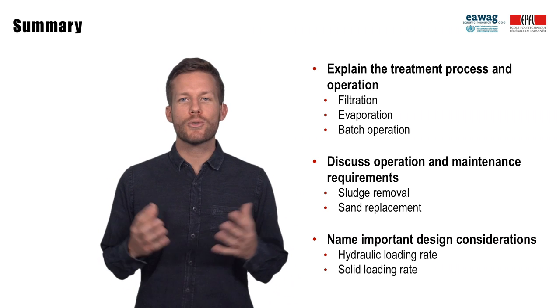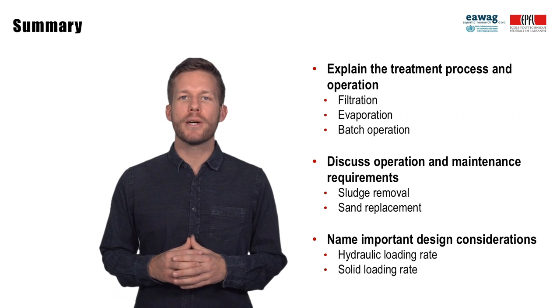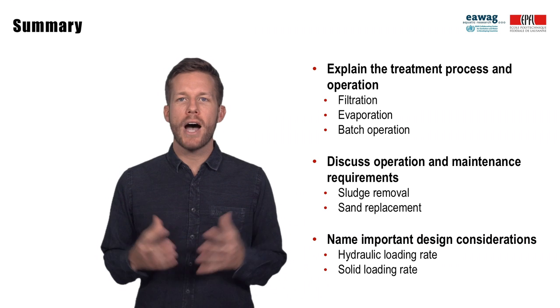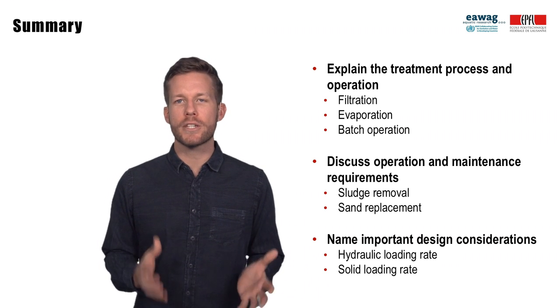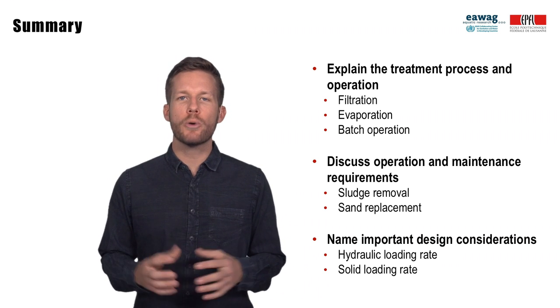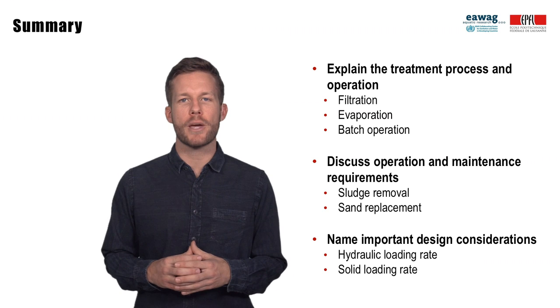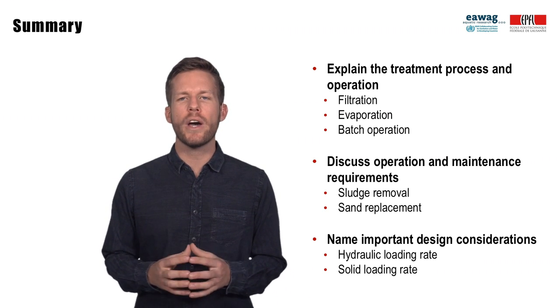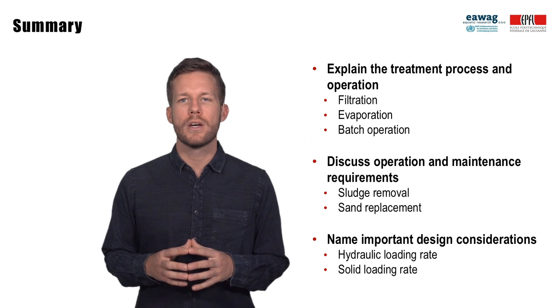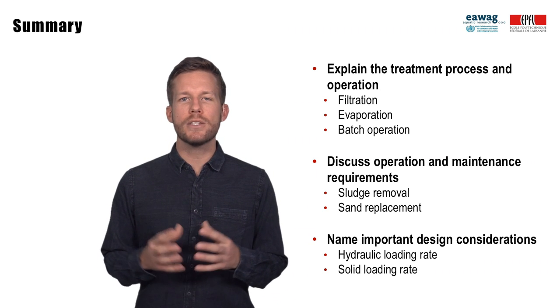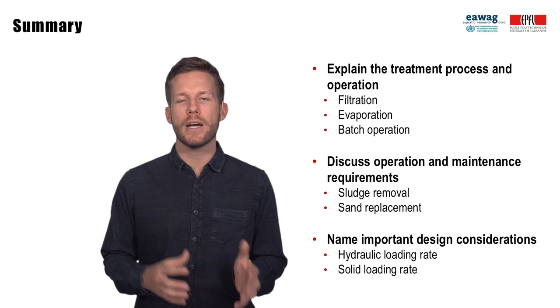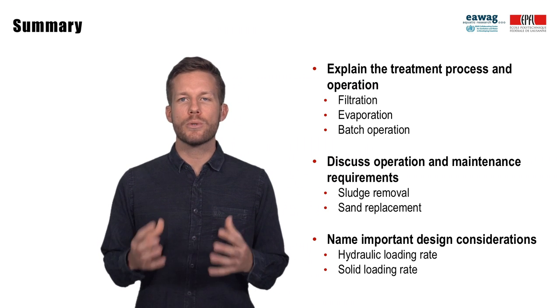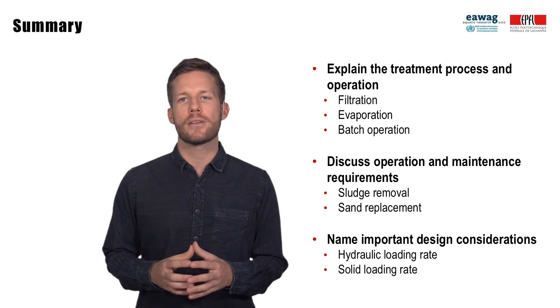In this module, we learned that the treatment process of unplanted drying beds is based on filtration and evaporation. Unplanted drying beds operate in batch mode and require removal of sludge from the surface of the drying beds. In addition, the replacement of the sand filter layer is required for reliable operation. Drying beds need to be designed based on the local climate and sludge characteristics. The most important design parameters include the hydraulic and the solid loading rate.